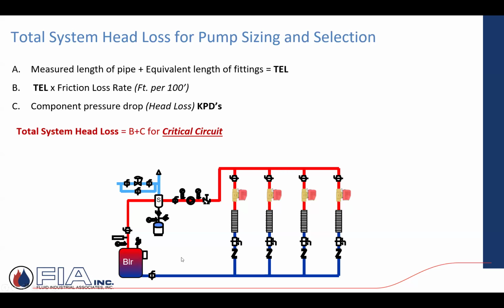And this is just a quick other example of that. Saying, hey, I got 4 circuits. I have a boiler. I have air separation. I have gauges. I have control valves or zone valves. I just want to calculate the TEL times the friction loss, right? What's the measured length plus the equivalent length of fittings? I want to figure this. What's my longest run, right? What's my longest run? And what's my component pressure drop of the longest run?